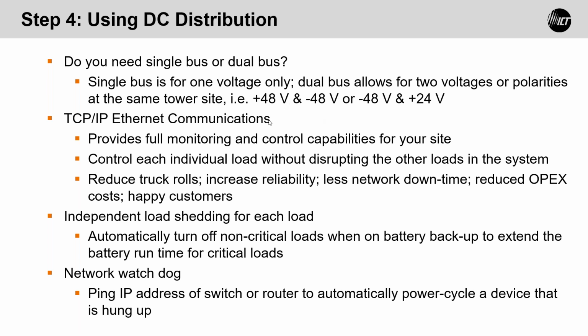So if we have a dual bus panel, you could have plus 48 and neg 48, or you could have neg 48 and plus 24 at the same site by the way you wire and configure a DC-DC converter that would be isolated, that would go in between the rectifier, the neg 48 rectifier, and bus B, for example, in the distribution panel. Also, you'd want to look for TCP/IP Ethernet communications in the distribution panel.